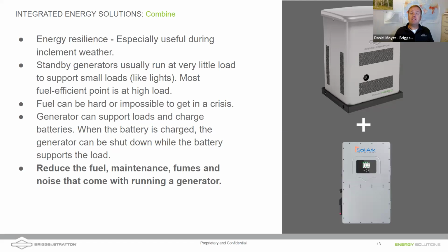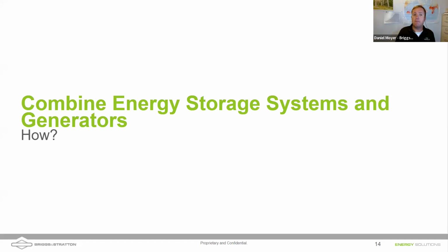So what we can do with energy storage is start up the generator and run it hard, at a more fuel efficient point, for maybe just 2 hours, to charge up the batteries and then shut the generator off. That really saves on fuel, which equates to cost savings, but also during a crisis, fuel may be more difficult to get. You might not get a propane truck down the road. When that generator does start up, it's going to take over the support of those loads and then charge those batteries up.